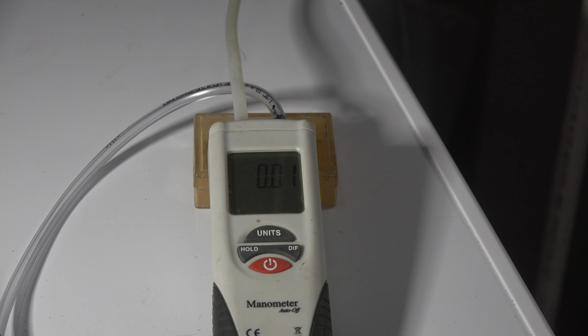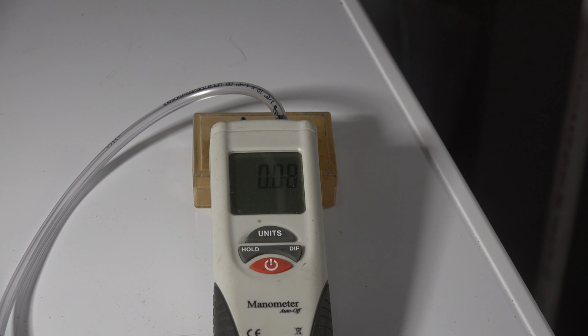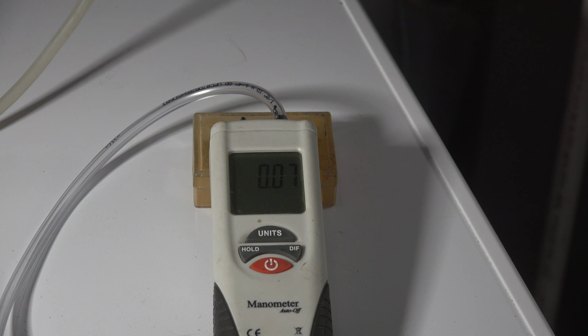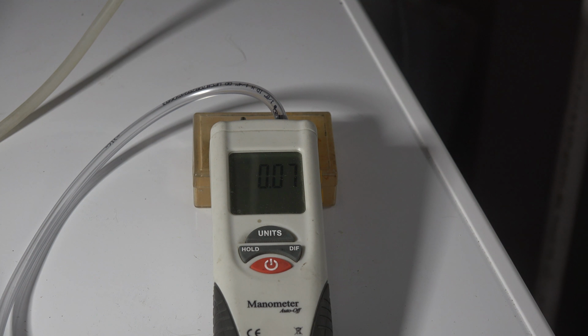Now you can see I'm running 0.01, very small drop. Now understand, we don't have a lot of pressure drop in the supply at all. If I disconnect the probe downstream of the T, you can see my total static on this whole thing is 0.08. So once I've gotten past that coil, I've got a very low static pressure, and I've lost 1/100ths going across that T. So there's really no sense in going farther in looking at the supply, because it is very, very low. But what we can do is look at the other side and see if there's any problem. Now I want to note that there isn't much here, so I'm probably not going to find anything on the other side either. It's very low, but we'll check it anyway.